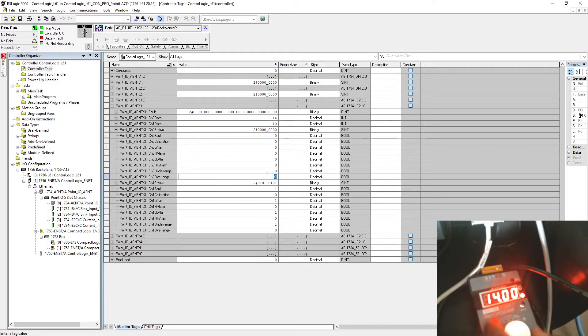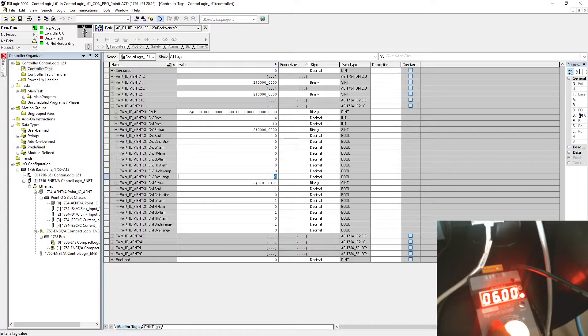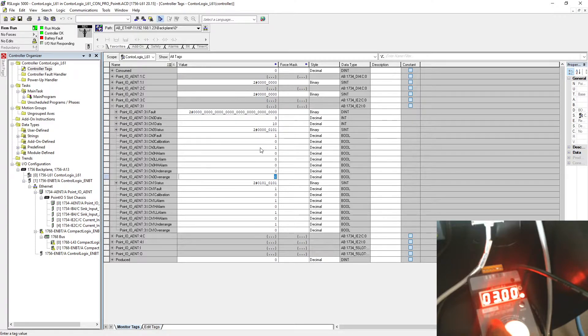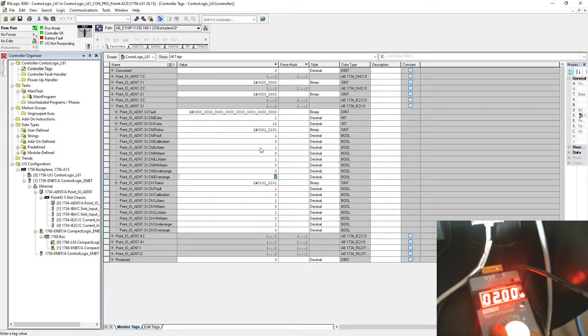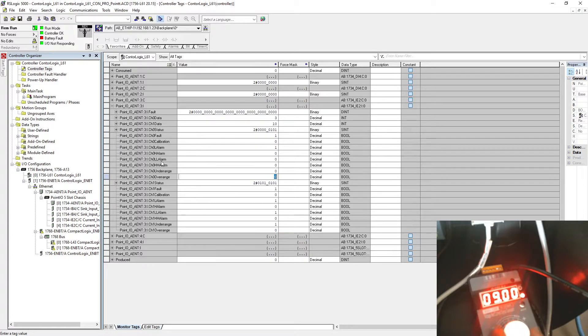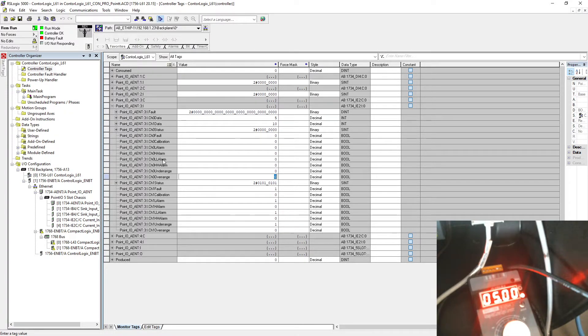Let's see if our low alarm and low-low alarm is working. We go under 4. There you go, my low alarm turning on. When I'm under 2, my low-low alarm will turn on. Low alarm and low-low alarm is working, and high-high alarm is also working.